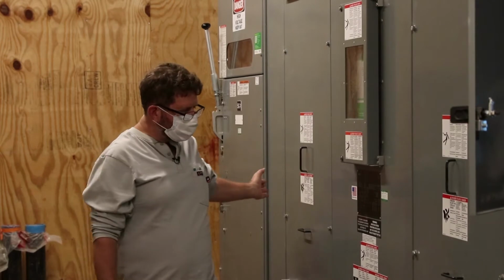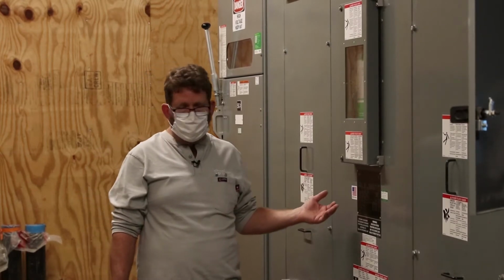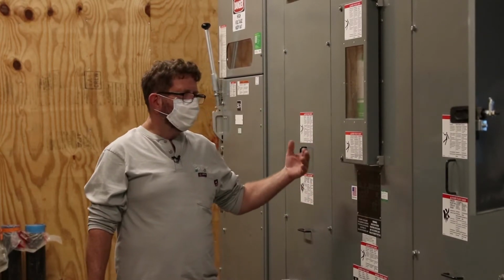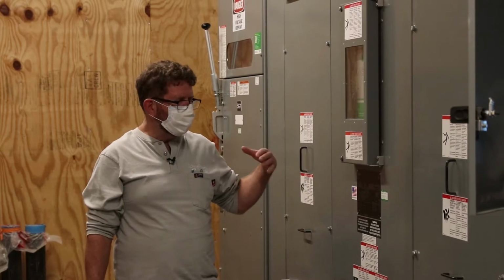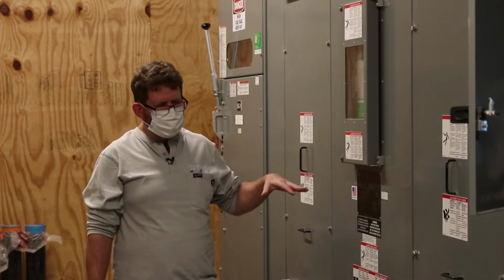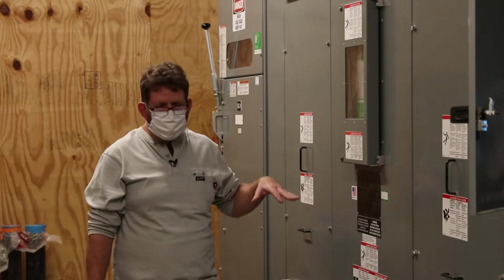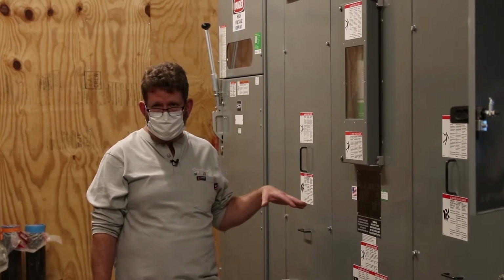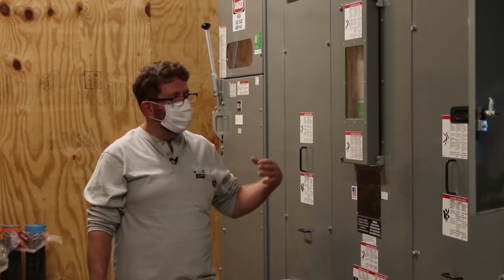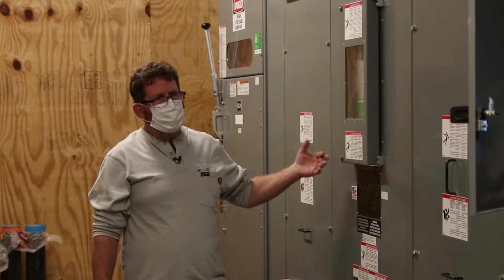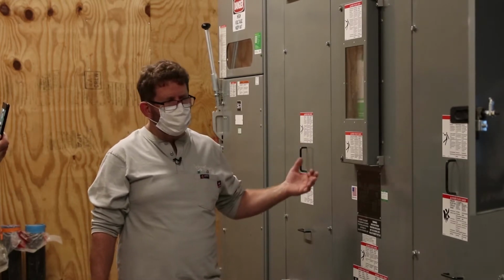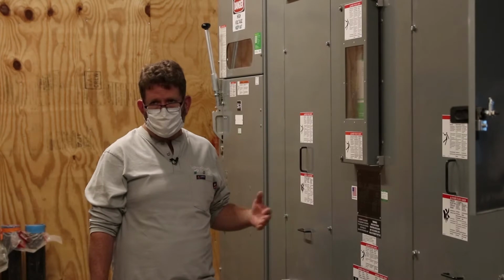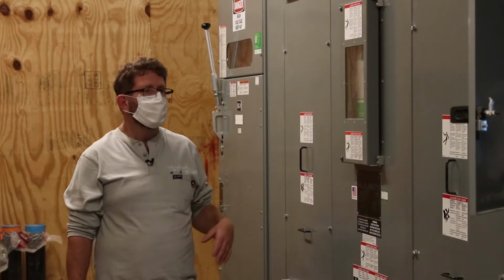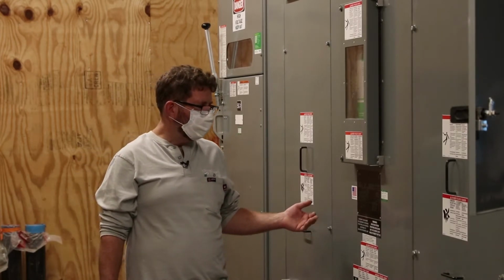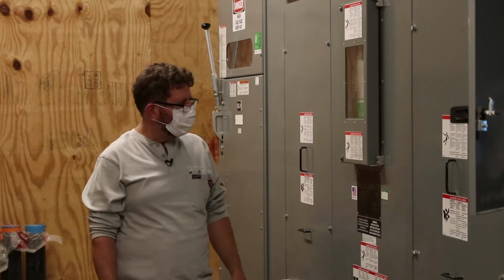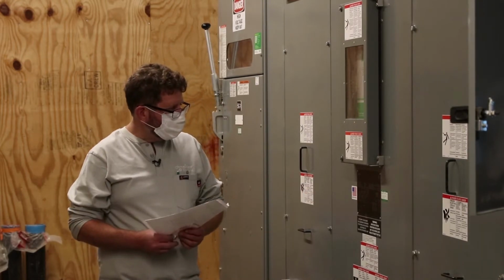There's not much to do with the transformer. We may recommend, like the switch, maintaining it once a year. Vacuum the coils. We highly discourage use of compressed air when you're cleaning a transformer. Some people will do that. What we've found is you can drive dirt and dust into crevices in the transformer that you're never going to get out of. So it's best to just wipe it with clean rags and vacuum.